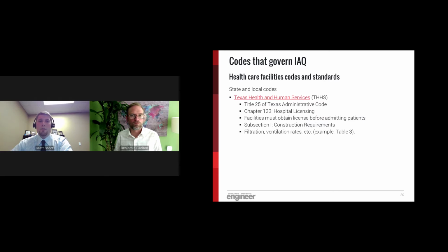An example of these amendments can be found in the ventilation tables, which in the Texas code, which I mentioned earlier, is Table 3, where some spaces may have different required air change rates than what's described by ASHRAE Standard 170. And so now, Benny, I think you'll discuss further requirements on indoor air quality.